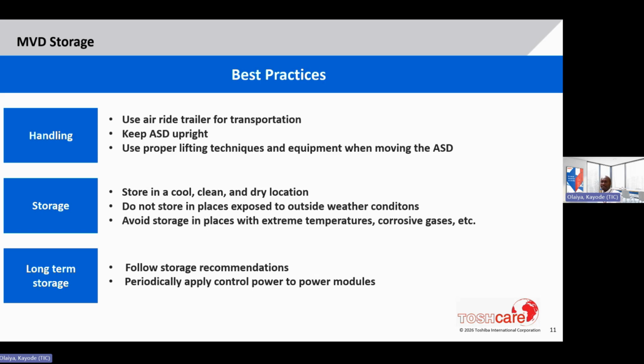Storage, if needed, should be in a cool, dry location, and should not be subjected to extreme temperatures. And for long-term storage, the regular storage rules apply. In addition, we recommend periodically applying control power to the power modules to make sure that the boards with electrolytic capacitors are getting a charge. We would say once for 30 minutes every 2 years would be enough.